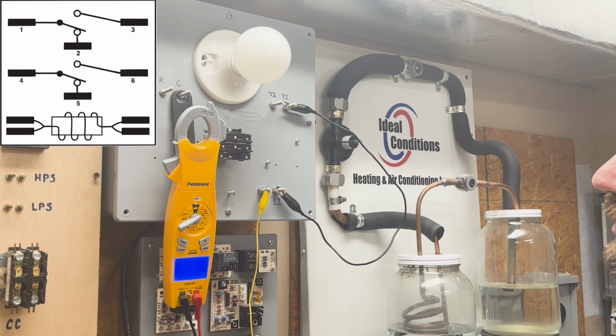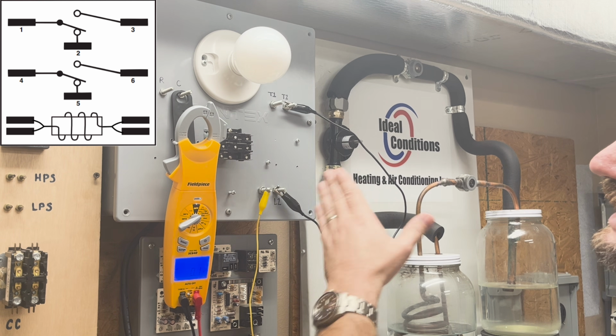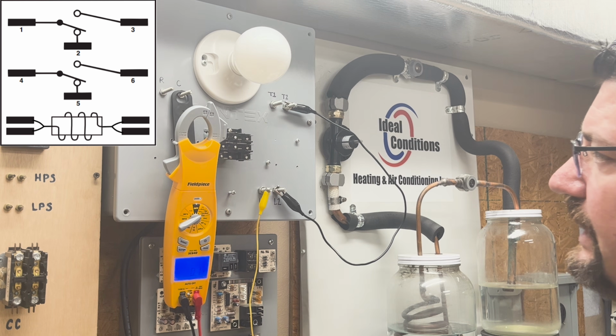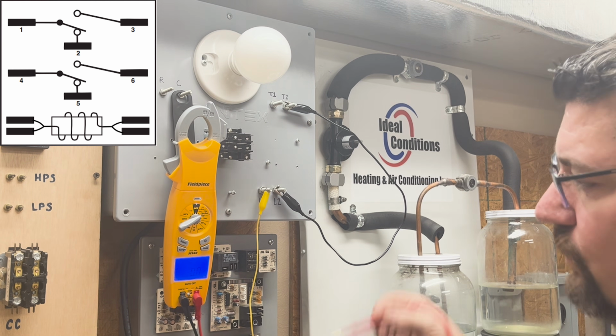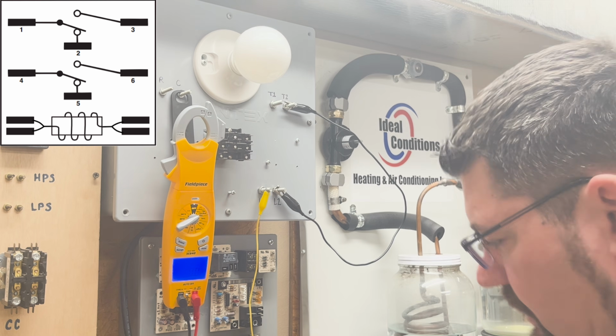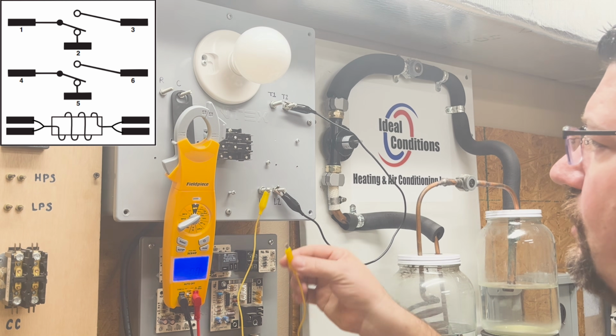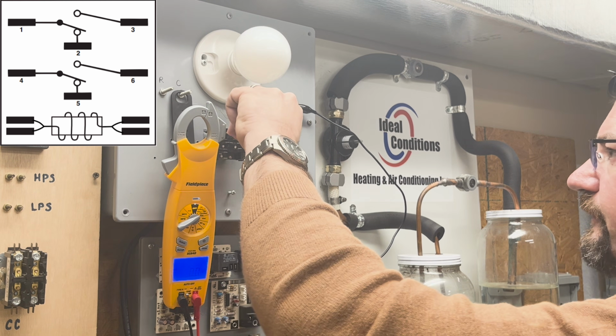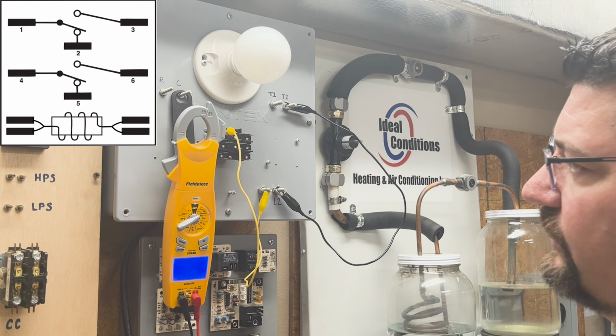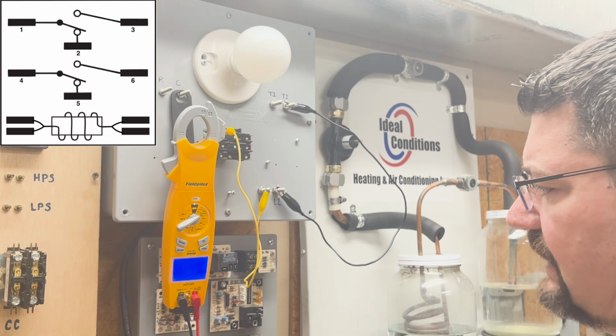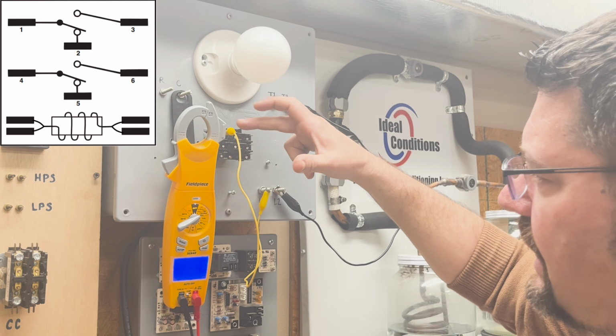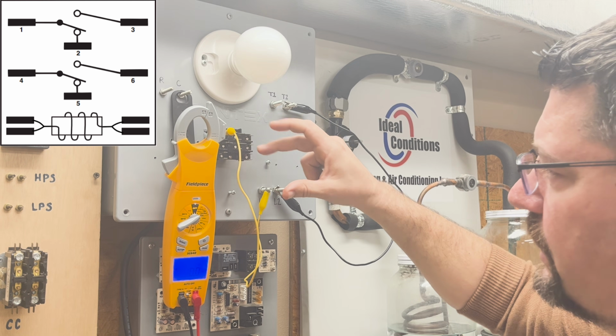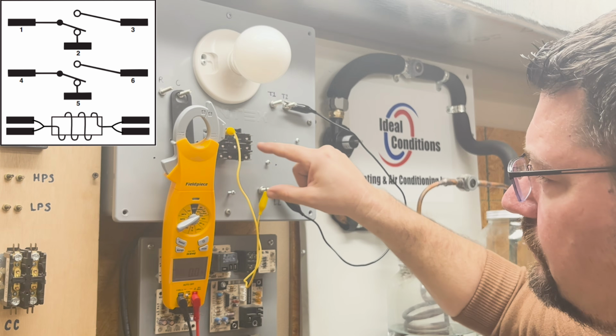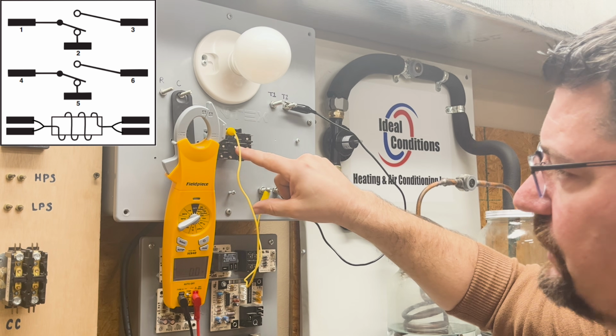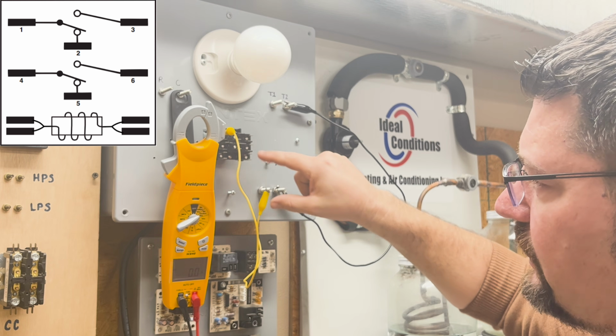So it's very important when we're running power through relays - I'm going to show you how we can still see what we just saw here on this relay. We can go across a couple of points and read 240 volts. So we're going to get into it, and I'm going to take L1 and wire it up to the first terminal on the top left-hand side of the relay - it's called terminal 1. That's going to be a line voltage terminal. This top portion of the relay is one pole. The second portion of the relay is terminal 4, which is line voltage, and then I have a switch on 5 and a switch on 6.